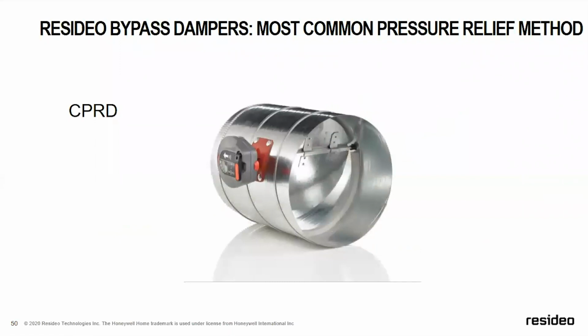CPRD, this is for bypass. Now, you really want to use bypass when you're dealing with the ECM motor, because ECM motors have a safety in them that if you go above 1.5 static pressure, that blower motor is going to think your coil is freezing or your filter is plugged, and it's going to ramp up to 2.0 for the duration of the call. Now, in my market in the Chicagoland area, I quite often get calls from contractors that say, your zoning is terrible. Every time this thing calls, it sounds like a jet engine. Typically, I will go out and they sized the bypass wrong. When the bypass is sized properly and you start up, your bypass is going to open, your motor is going to get past startup, and then it's going to ramp back down. Your bypass is then going to close.